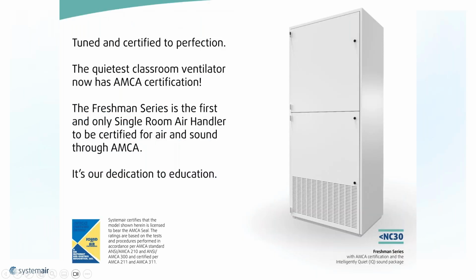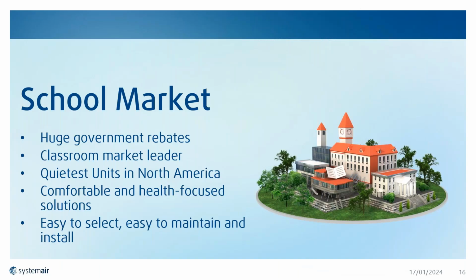So what we developed is our freshman series, and if you apply the IQ package to it, you could get NC 30. This freshman unit does not have a compressor in it. We're going to show you later how with a compressor package unit you can even get NC 35. This unit, in particular, you could have with hot water hydronic, chilled water hydronic, etc. It has the AMCA label, as you see at the bottom left. The AMCA certified rating says that this unit is certified and accredited with AMCA to perform at this sound level in an AMCA accredited chamber. We have the data to back that up, and we can provide it for any job when it's in design.